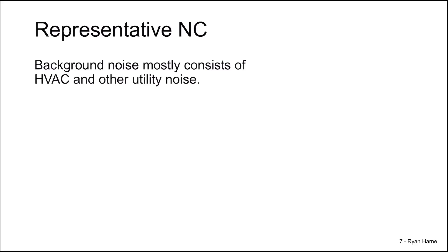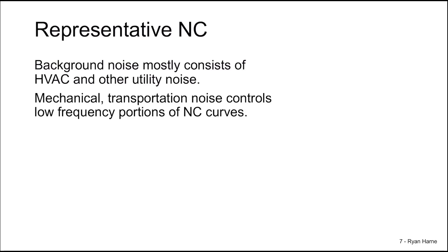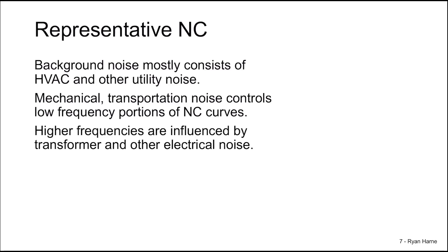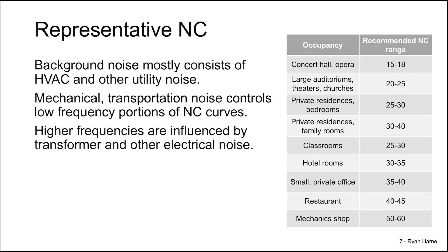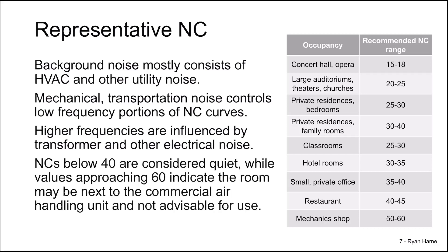Background noise mostly consists of HVAC — heating, ventilation, and air conditioning noise — or other utility noise. Mechanical and transportation noise in the room mostly controls the low frequency portions of the NC curves, whereas the higher frequencies in the NC curves are largely influenced by electrical noise, for instance electrical transformers. If we consider the relationship between NCs of a room and recommended use, we find that for rooms where high privacy and clear speech is needed, very low NC values are recommended. NC values below 40 are considered quiet, while values above 60 indicate more of an industrial or heavy commercial space close to air handling units, and is not generally advisable for day-to-day use.